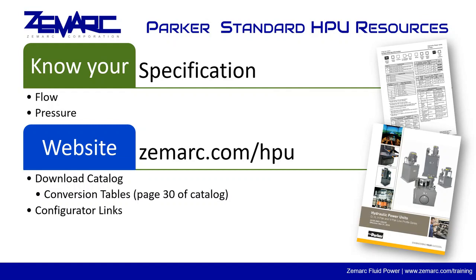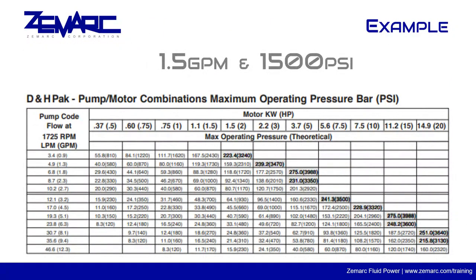We would then reference page 30 of the online catalog to determine which pump and motor are sufficient for this application. We can see, according to this chart, that we will need the 1.8 GPM pump to meet our minimum flow requirement of 1.5. And if we follow the row to the right, just right there, the 2 horsepower motor provides enough power to accommodate 1700 PSI, which meets our minimum pressure requirement of 1500 PSI. So there we have our pump, we have our motor. I'll talk a little bit about the reservoir in a little bit.